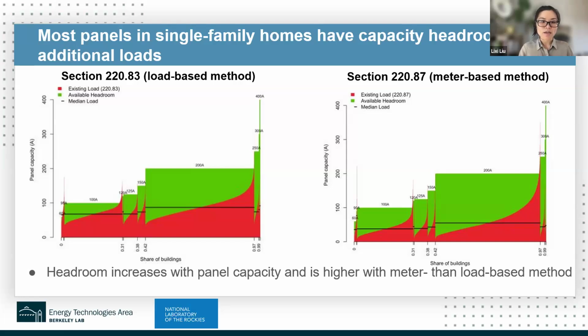The second takeaway is that about 2% of homes here show a connected load exceeding their panel rating. That's visible as the red spikes on the right tail of each size bin. While some may reflect genuinely overloaded panels, this is largely a modeling artifact due to inherent uncertainty. The service rating was predicted from limited housing characteristics rather than the detailed equipment list and sizes used in the NEC calculation. So these 2% of homes do have a pre-existing capacity constraint under this framework, which is a caveat to keep in mind when interpreting our results.